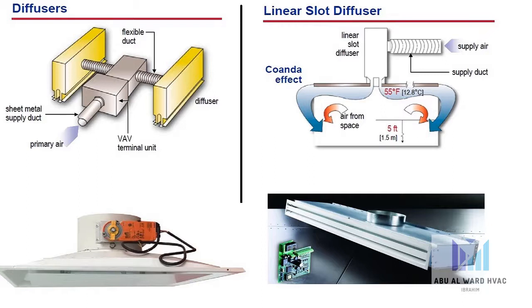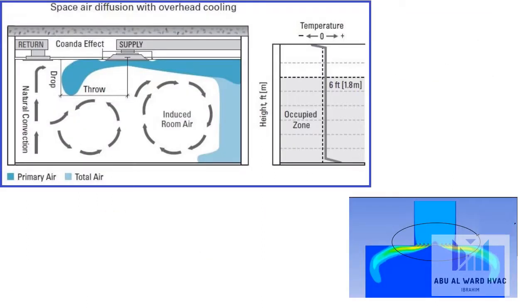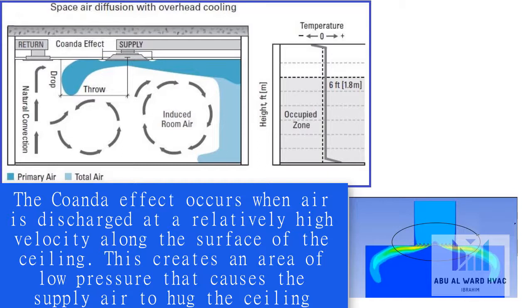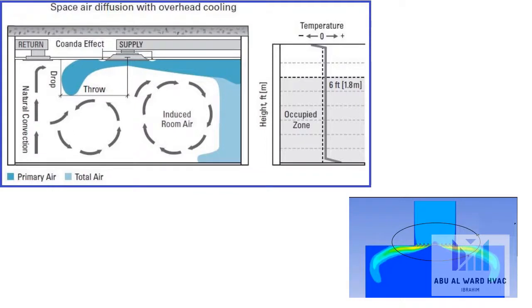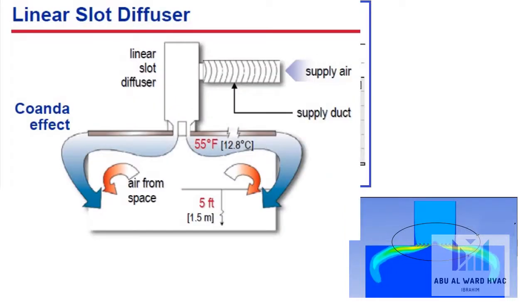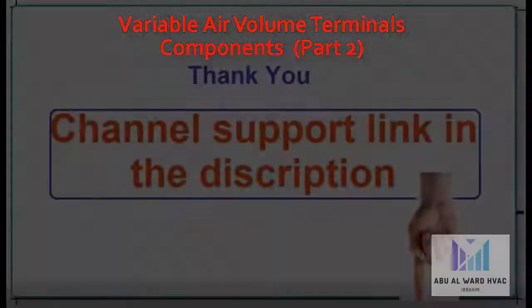Linear slot diffusers are generally preferred for VAV air distribution. They use a principle known as the Coanda effect to distribute air to the conditioned space. The Coanda effect occurs when air is discharged at a relatively high velocity along the surface of the ceiling, creating an area of low pressure that causes the supply air to hug the ceiling. As it travels along the ceiling, air from the space is drawn into and mixed with the supply air stream. When the air settles to the occupied levels of the space, it has reached an average temperature. The design of linear slot diffusers allows them to effectively distribute air over a wide range of airflows, making them the preferred diffuser for VAV systems. They also offer acoustical benefits over other types of diffusers.